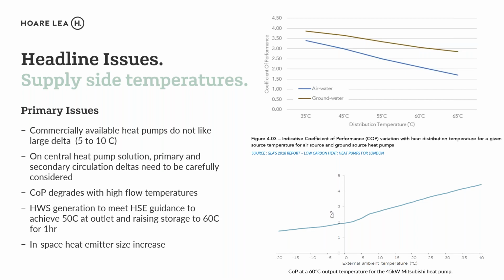Hot water generation is the key. I know there's been some questions on that already, but it has to meet HSE guidance. There's no way of getting around that: to achieve 50 degrees C at the outlet and have the storage, if there is storage, raised up to 60 degrees C for 1 hour. And obviously the other issue is that with reduced flow and return temperatures, your in-space emitters start increasing in size. But obviously a lot of heat pumps are associated with underfloor heating, which only takes 45 degrees, which is a good heat pump match, but is very expensive as a form of heating an apartment.